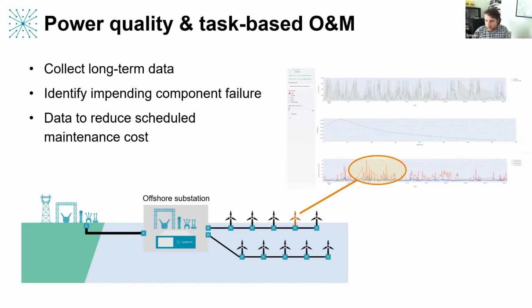So for example, in the right-hand corner, we're looking at some actual data we've recorded from one of our systems, and we can see that we can detect when one harmonic does something unusual that it doesn't normally do. We can use that information to alert the operator that this is perhaps indicative of a control issue, or it could be a component failure, or it could be a reason to adjust the maintenance schedule.